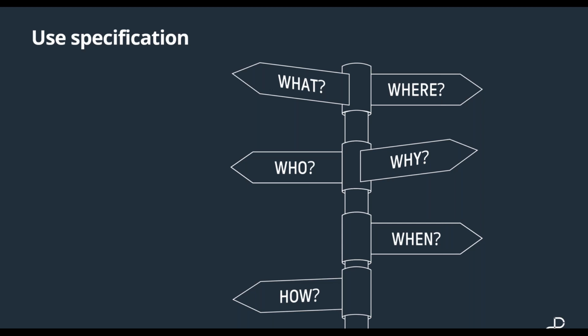Also in the use specification is a description of what the user interface is at a very high level, what all those buttons and switches are on the final version of a product, what the purpose of the product is, why, what need it is filling, when it is used, in terms of the use scenarios, what point in a medical procedure or process this product is used, and also how it's used, in what ways users are interfacing with it, and what it is doing.